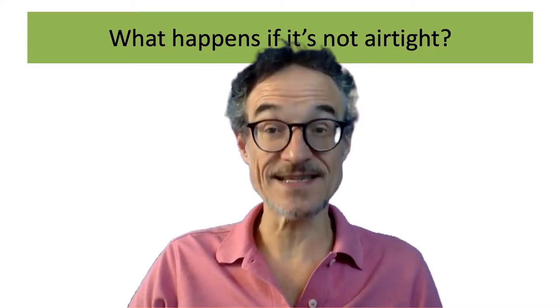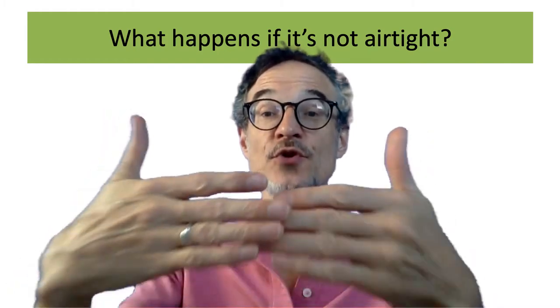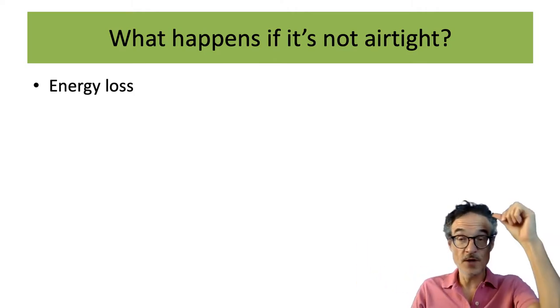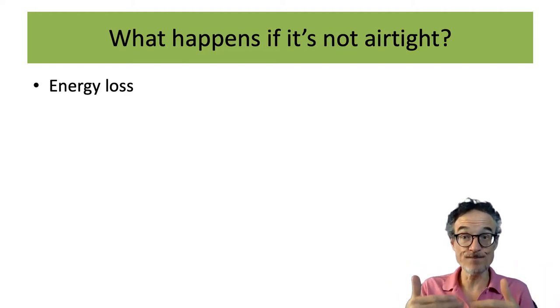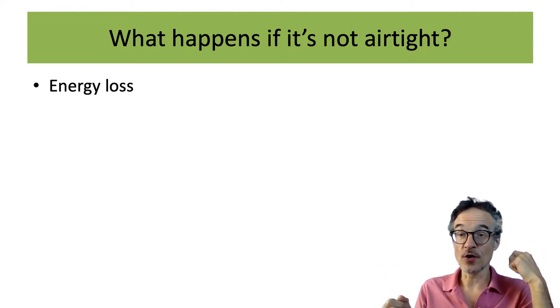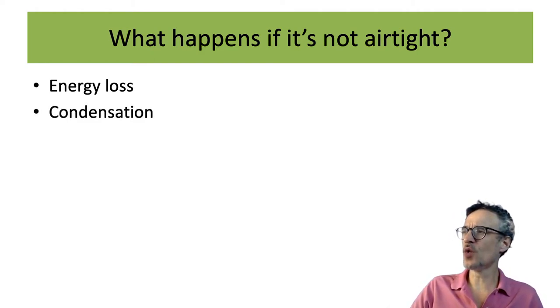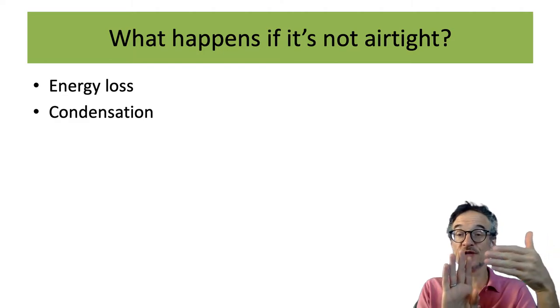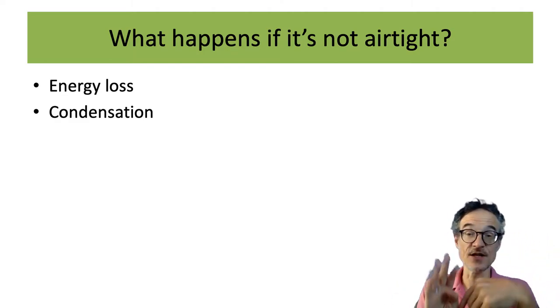So we know how to measure airtightness and insulation. What happens if a building is not airtight — if it's leaking air through the walls? Two things can happen. First, if it's winter and your house is warm inside, any air leaking out means you're losing heat. If it's very cold outside and warm inside, you'll lose lots of energy and need extra heating to make up for all the warm air leaving. Also, as hot air moves through your walls and cools down, there's a risk of condensation forming somewhere inside the wall.